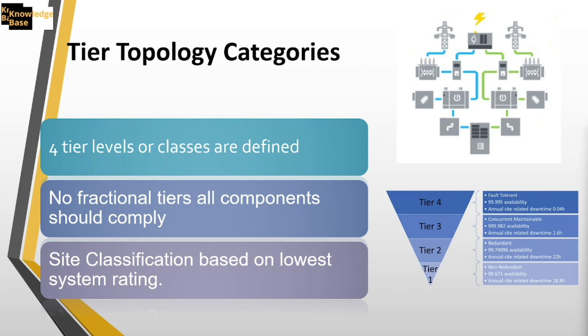Data center tiers provide a concise way to convey essential details about a facility. They establish expectations and set clear parameters for cost, availability, and redundancy. When you hear tier three, you know it's concurrently maintainable, with 99.982% availability and a downtime expectation of 1.6 hours per year. When hiring a co-location data center, if it's tier three you know exactly what quality of service you're guaranteed.